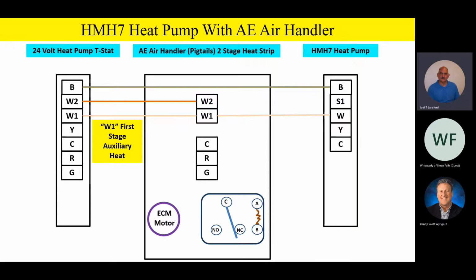Now, you'll also notice you're going to carry that outside, because remember, team, you're going to want to bring on some auxiliary heat during defrost. So the outdoor unit will generate a W call during defrost to bring that heat strip on, so you don't freeze the homeowner out when it goes into defrost. Because remember, anytime a heat pump goes into defrost, what does it do? It goes into the cooling mode of operation, doesn't it? So we want to bring on some heat so we don't freeze the homeowner out during that defrost mode of operation.